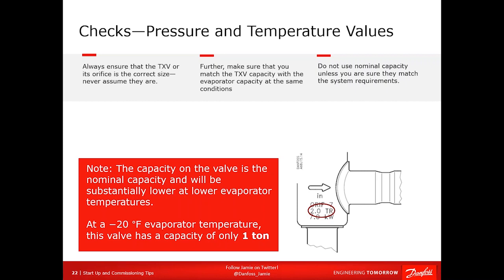So the rule here is just like compressors. Size the orifice, the TXV, for the unit cooler or your evaporator capacity at the expected operating temperature. So if you're going to run this thing in a super frosty ice cream cooler freezer, make sure you size it for that minus 20 or 25 temperature. Otherwise, you're never going to feed that evaporator and you're going to have problems.